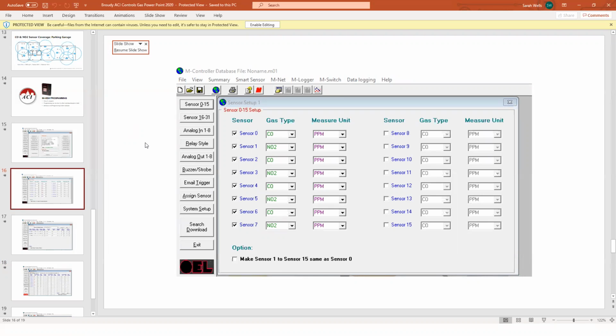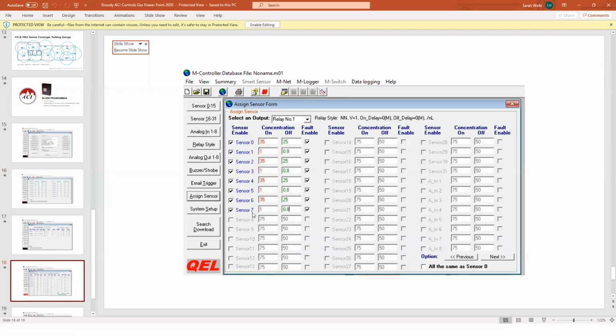Okay. But anyway, I went back to the other slide because as you can see there's the sensors 0 through 7. And then by coming back down here, 0 through 7, and they're all on, from the M controller, they're all on relay number 1. So just to give you an idea how that works. Any one of those sensors hits those concentration levels, that'll click that relay, and whatever fan or fans you have will turn on and go from there.